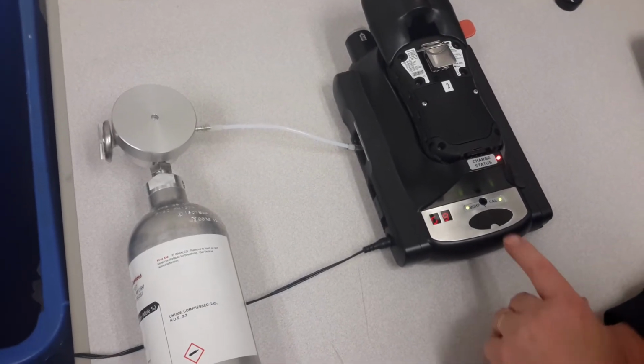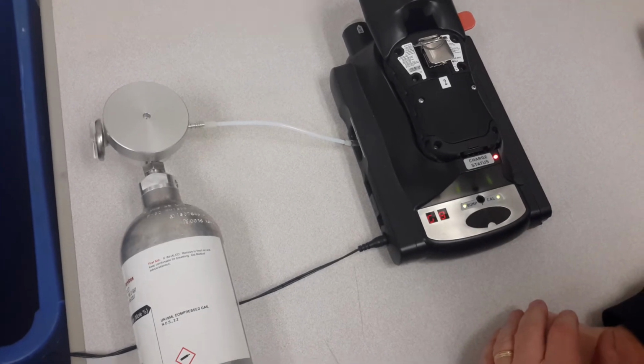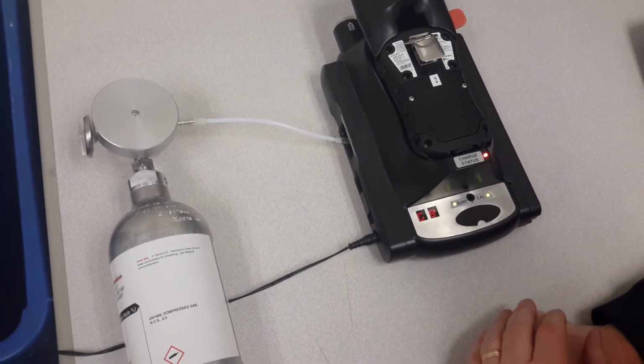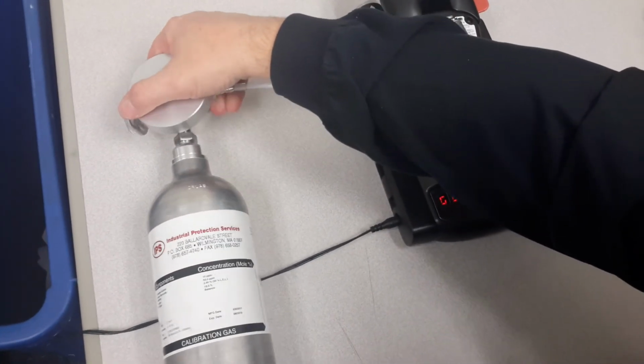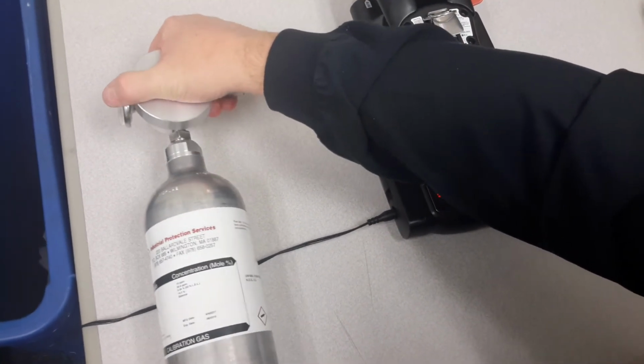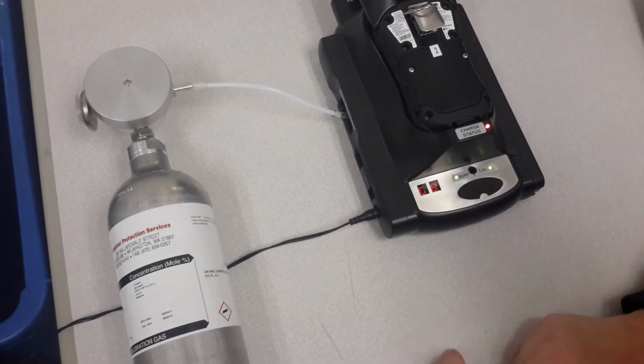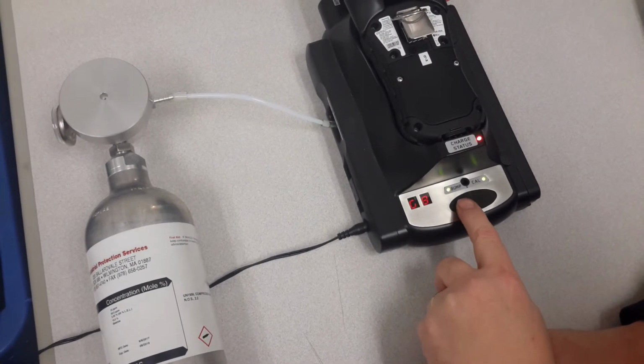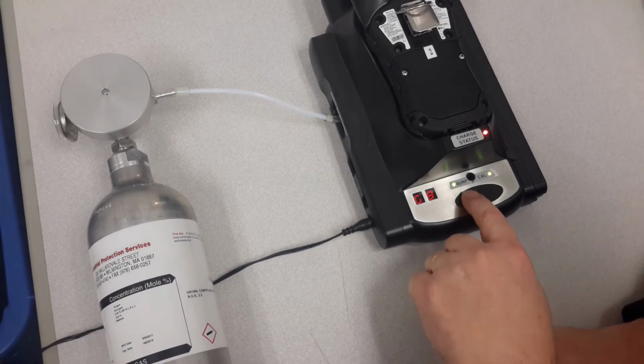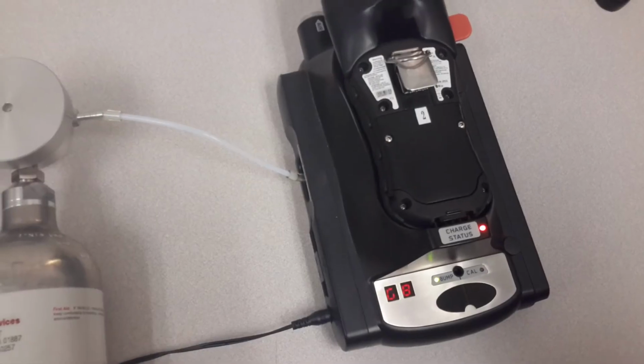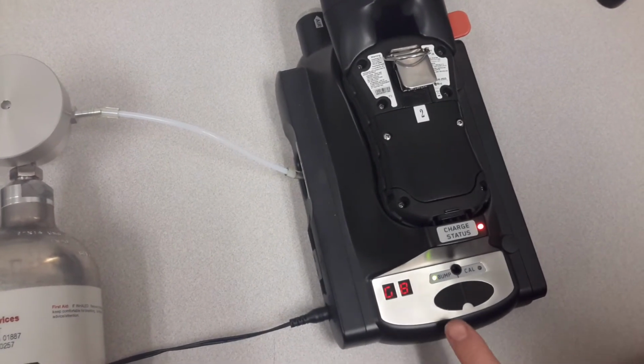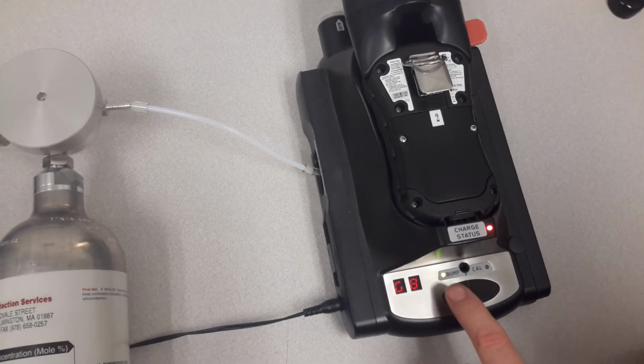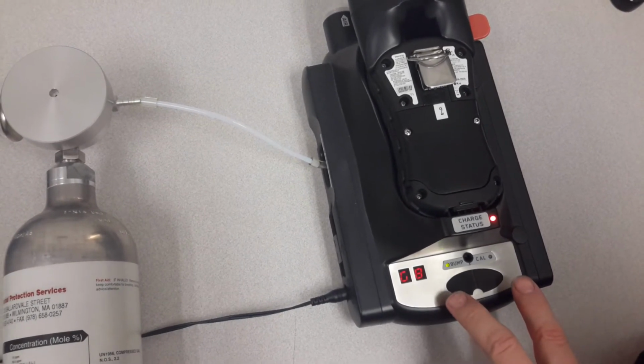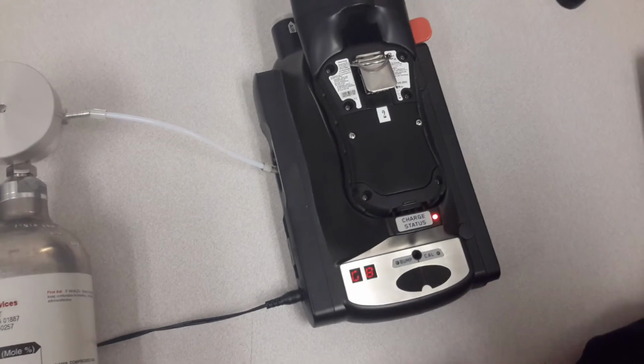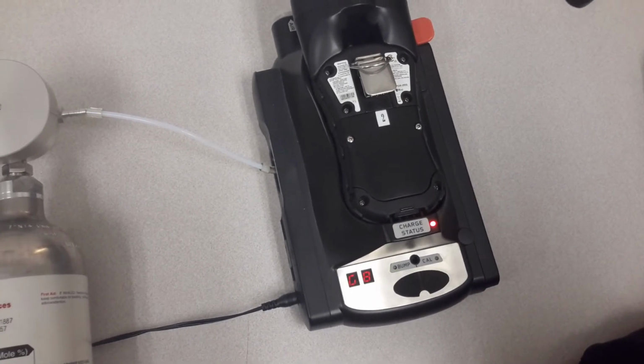Okay, our meter is warmed up, and you note here that we have 2 green LEDs here for calibration. So what we'll do is we'll move over to the gas bottle here, go ahead and tighten up the regulator, start the flow of gas, and then we'll go ahead and press the bump for calibration. Okay, so we've pressed our bump test. You'll see that one of the flashing lights will go off for calibration, and now it's working in the bump test mode.